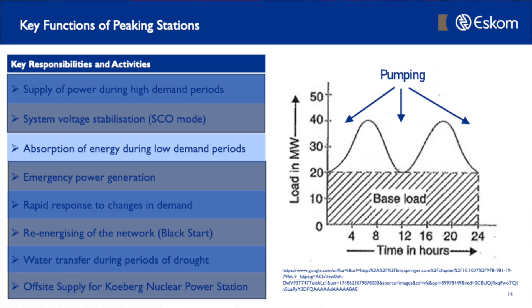Another absolutely critical function in supporting the system operator is that we can do emergency power generation. Sometimes in the grid we are operating at a maximum continuous rating, and there might be an incident, or an increase in demand, and the system operator needs extra energy. Our units are able to, for a limited period of time, between 30 and 60 minutes, ramp up to unity power factor and go to absolute maximum, beyond the maximum continuous rating.